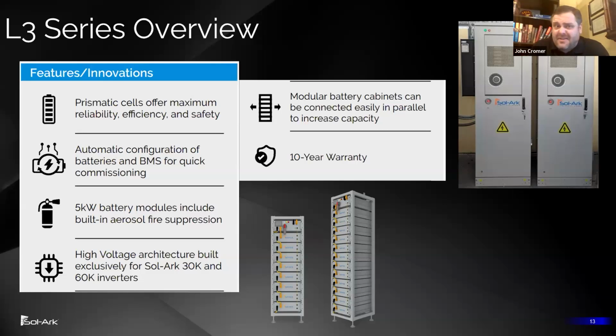We select prismatic cell structure, which is the most rugged cell structure. That's often because we know our systems are going in outdoor environments, and we try to maximize reliability versus other cell formats such as pouch. We also have built-in fire suppression in our battery modules, and in addition, fire suppression built into the outdoor battery cabinet. And that fire suppression, per NFPA 855, allows you to get exempted from the water sprinkler requirements for battery rooms. So it's an aerosol-based fire suppression.